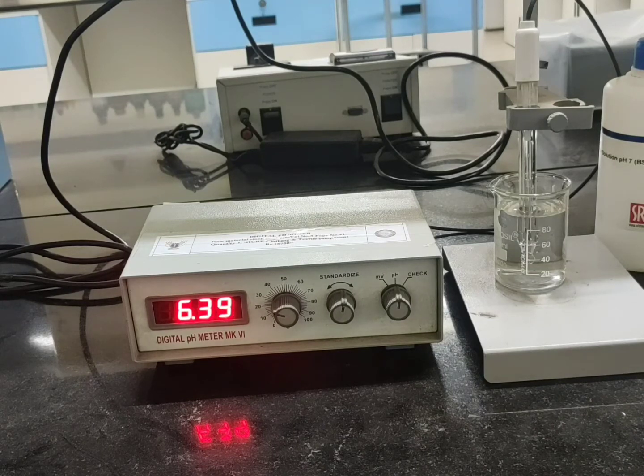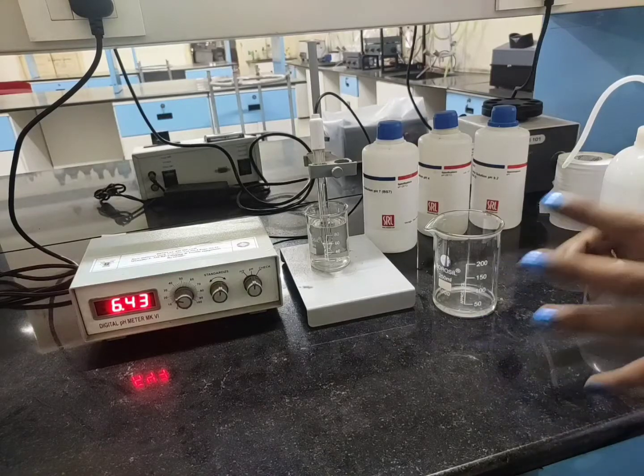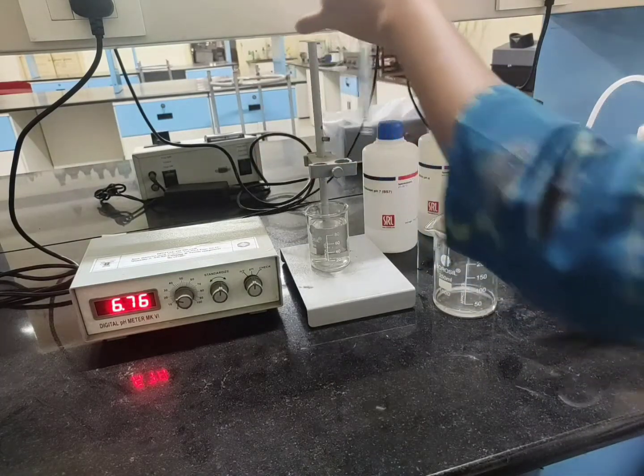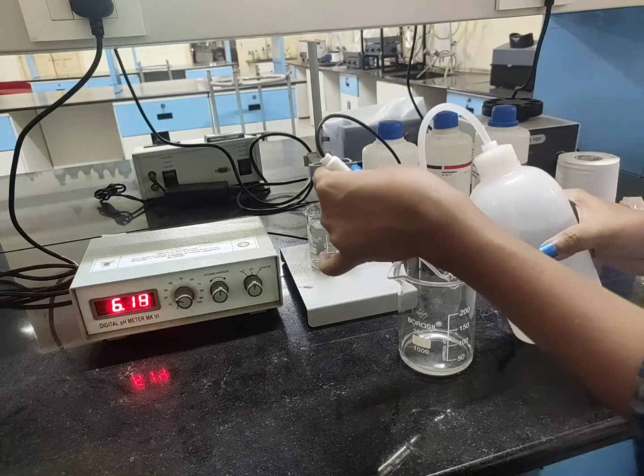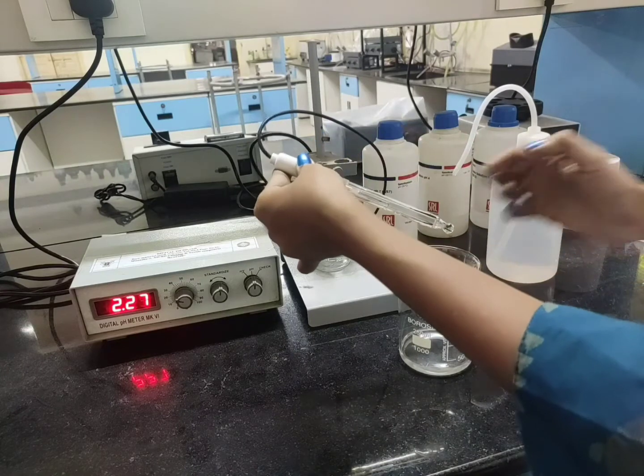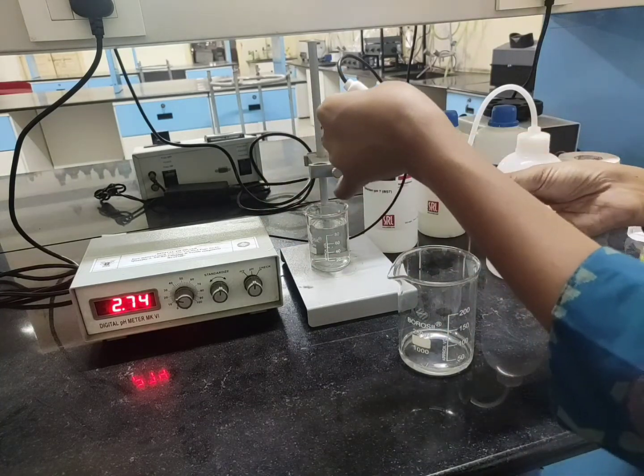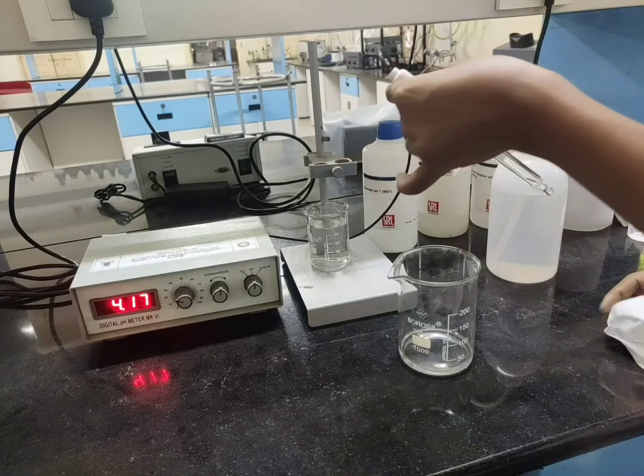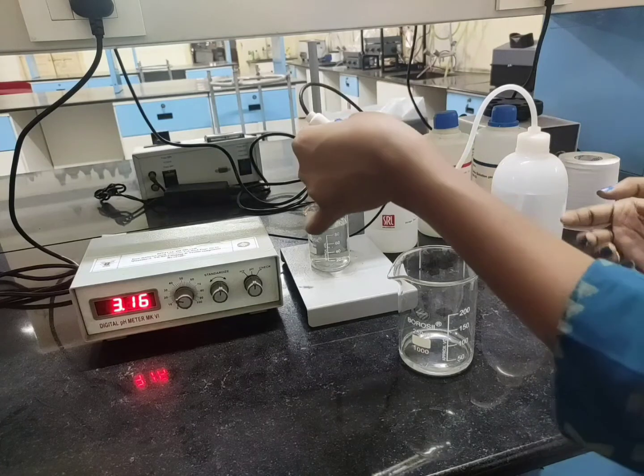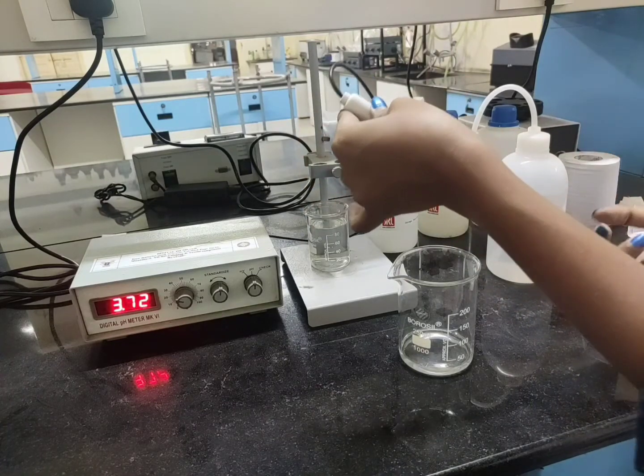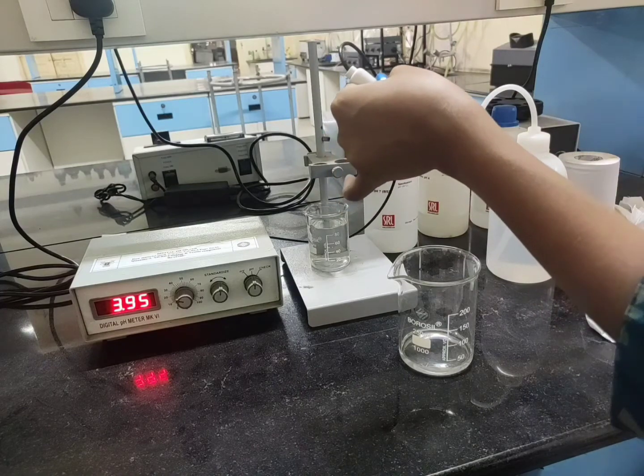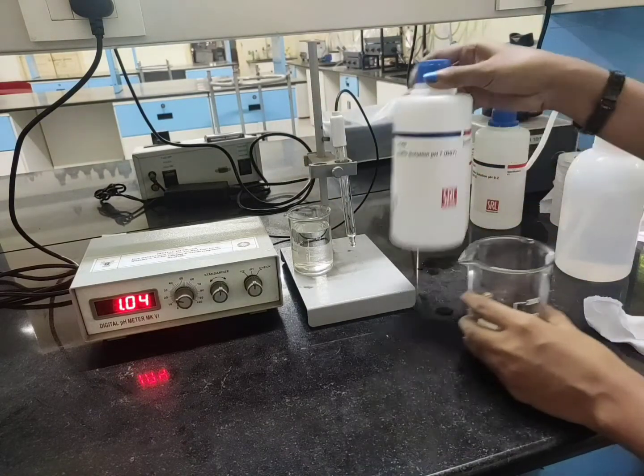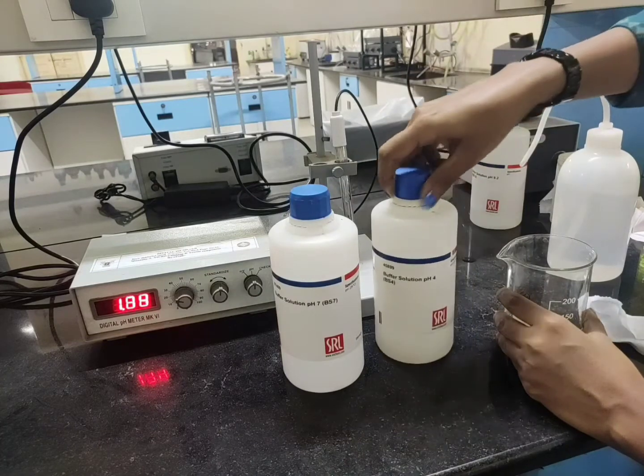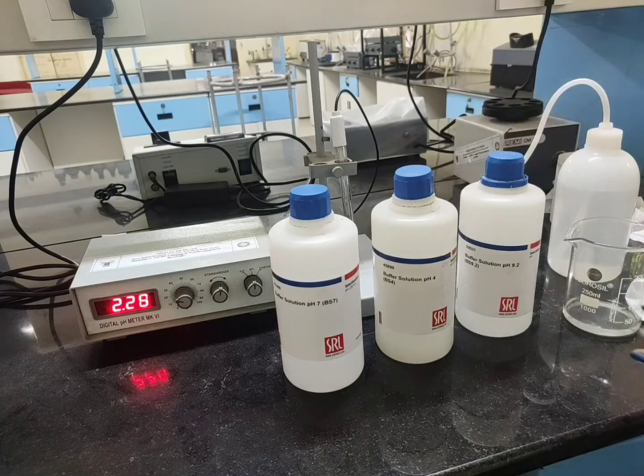Now let me show you how to calibrate the instrument. For calibration, the first thing that you are supposed to do is take out this probe and then you have to clean this probe. In this probe you see that there is this glass bulb which is very sensitive. While wiping or cleaning or handling this probe, you have to be very careful so that you don't cause any harm to the bulb. Once that is done, the next thing is you have to dip the probe in different pH buffers for calibration. The 3 pH buffers that we have are pH buffer of 7, pH buffer of 4, and pH buffer of 9.2. Those are the 3 pH buffers in which you have to dip your probe in order to calibrate.